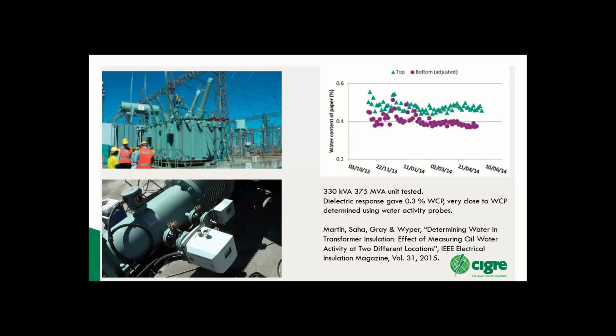So this was another one of our test subjects, quite a big transformer. We had 2 probes. We put one at the top in the pipe where the oil comes out to the radiator. There was one we put into the return pipe back into the transformer. These probes were both registering different temperatures, and that's just because one was in the flow of warm oil going to the radiator, and the other one was in the flow of cool oil going back into the tank.